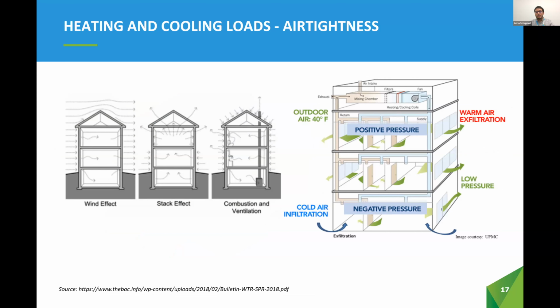There are many factors which influence air leakage in buildings, such as the effect of wind on the exterior enclosure, depressurization effects on the interior due to combustion or ventilation appliances, and the stack effect as warm air tends to rise. As buildings increase in height, the stack effect, thermal stratification, and pressure differences can become more pronounced. This tends to cause a negative or low pressure on lower level floors, inducing cold air infiltration, while positive pressure on the upper floors causes warm air exfiltration.